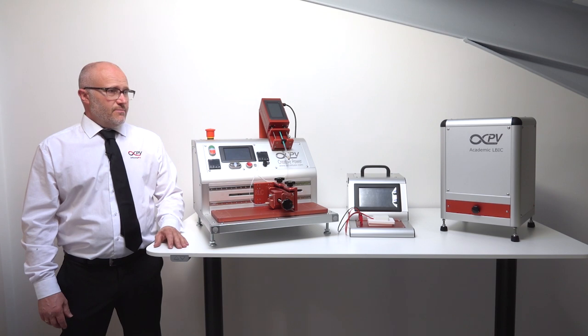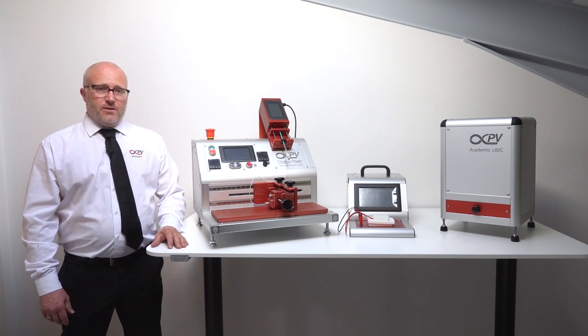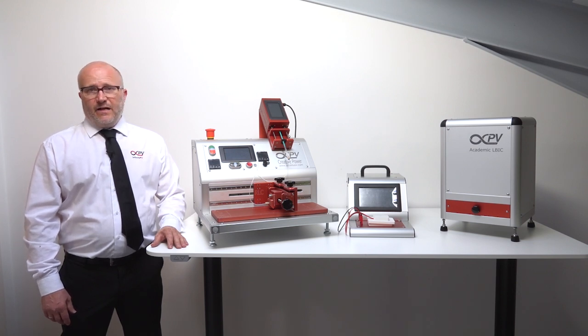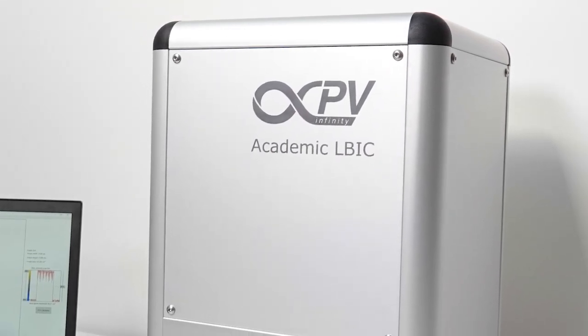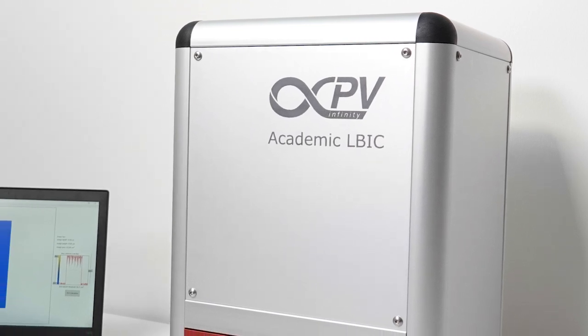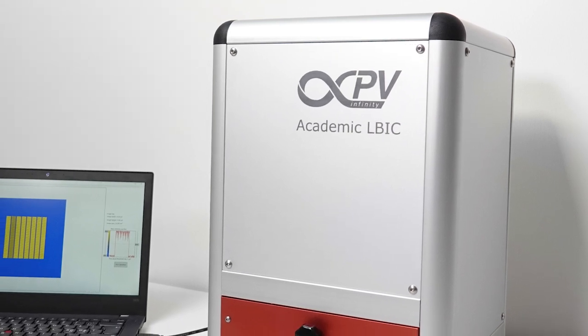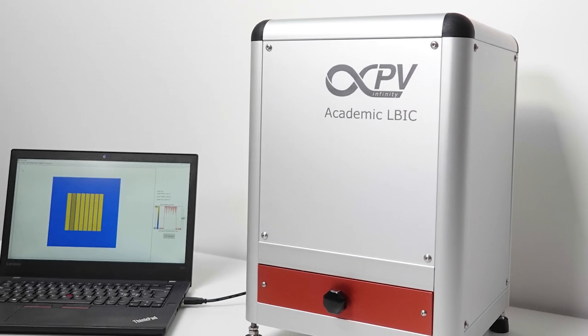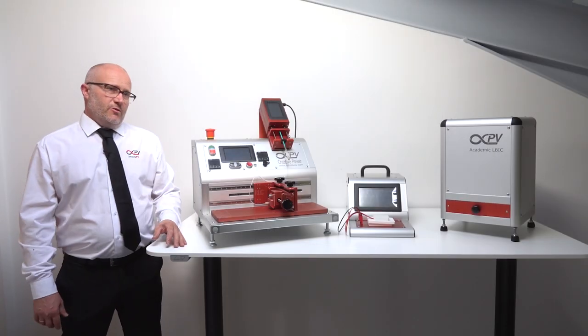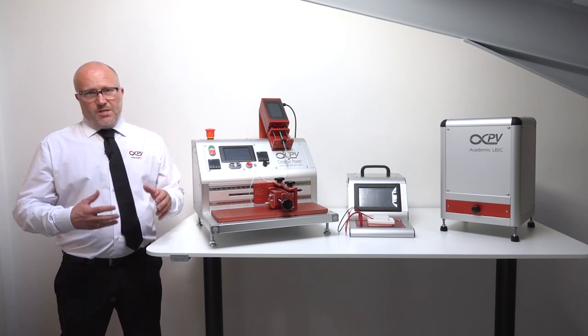The last system is the Academic LBIC. The Academic LBIC is a small Elbic, so it allows you to test a small device of five by five square centimeters, either a module or single junction. It is packed with all the power we have in our industrial series of Elbic equipment, except in a smaller size. There are some limitations in speed and you can only run with one wavelength, but we wanted the same power as the industrial unit on a smaller area with a simpler setup.